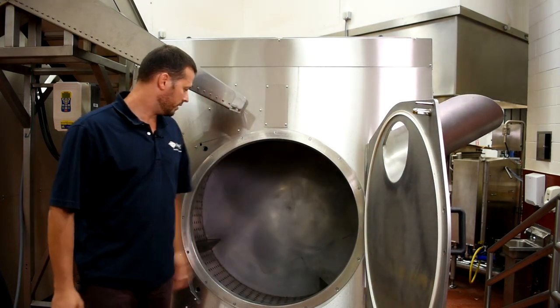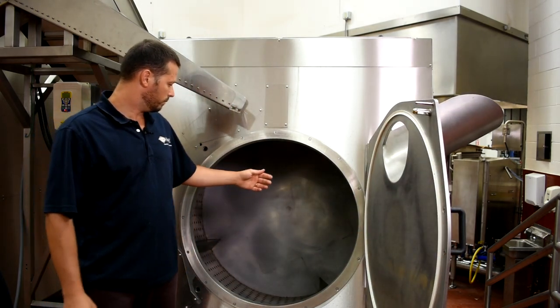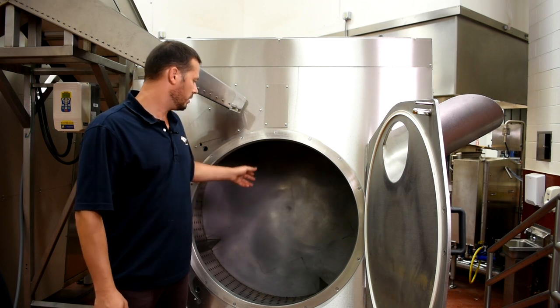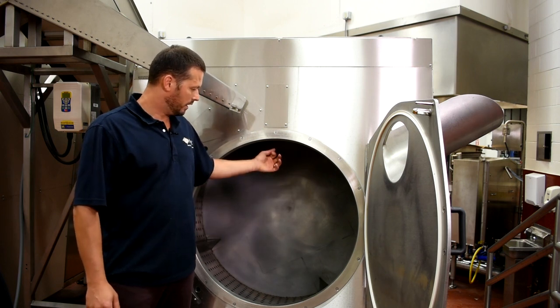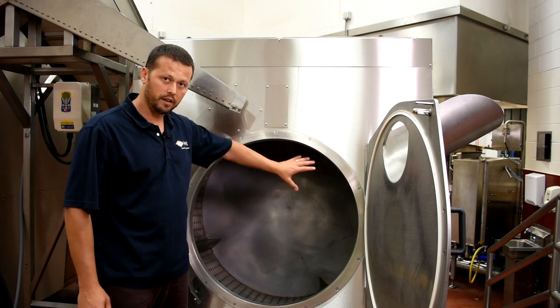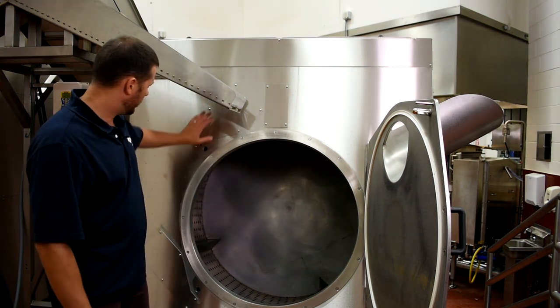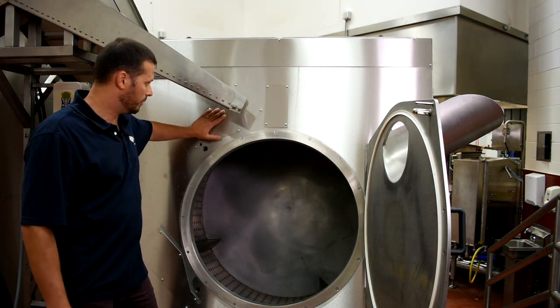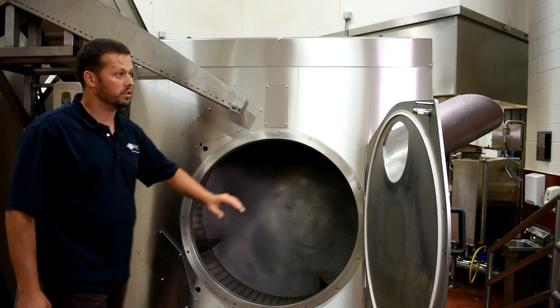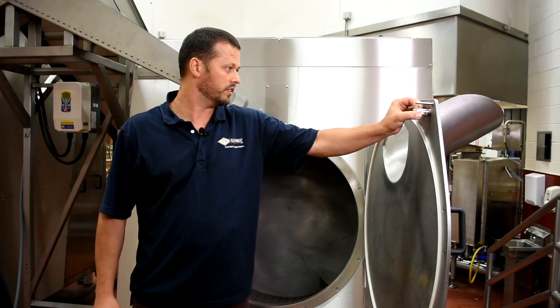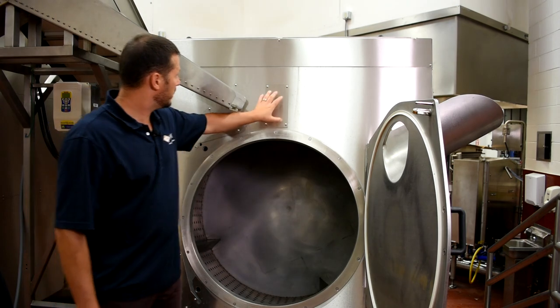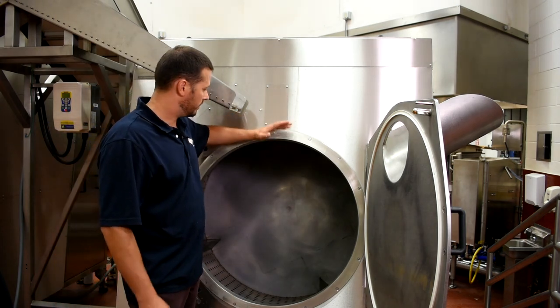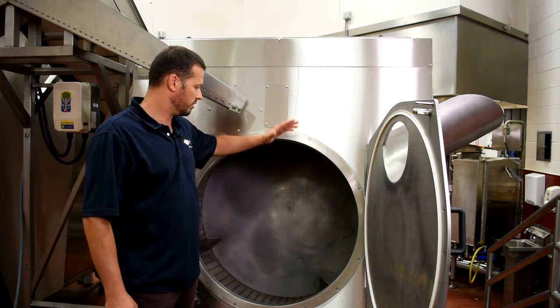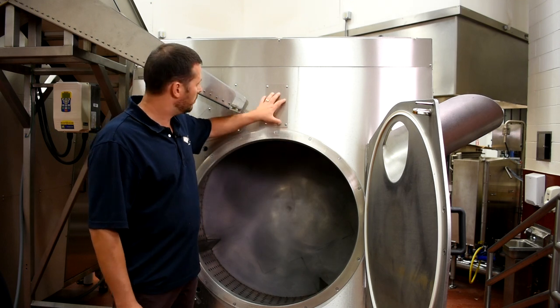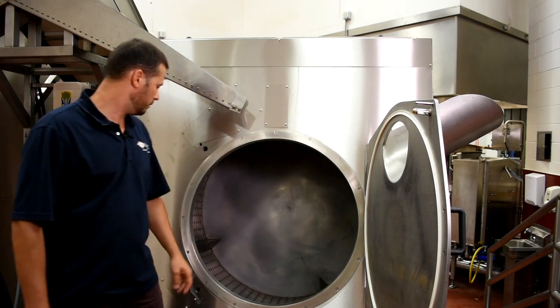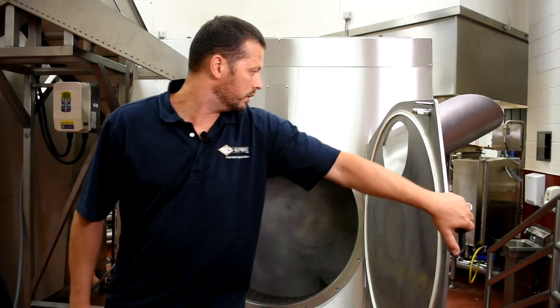Take a peek inside here. We've got a metal drum, all stainless steel. The level switches, the drain, and the water inlet are all behind this, so you can't really see them. Here we have the pneumatic cylinders closing the lid and holding it closed when it's locked. Also, right behind here there's an adjustment for if the tumbler wears out years from now, we can adjust it higher or lower. So we'll close the door and start the operation.